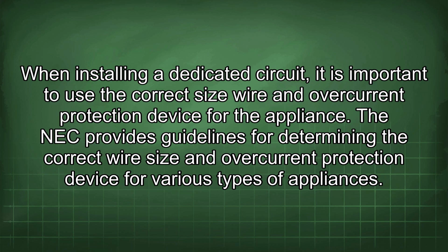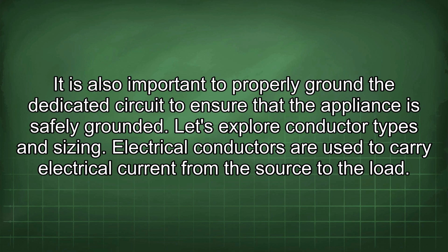When installing a dedicated circuit, it is important to use the correct size wire and overcurrent protection device for the appliance. The NEC provides guidelines for determining the correct wire size and overcurrent protection device for various types of appliances. It is also important to properly ground the dedicated circuit to ensure that the appliance is safely grounded. Let's explore conductor types and sizing.